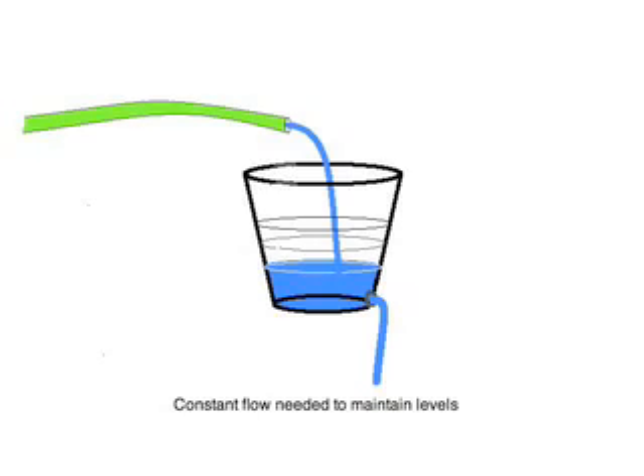With BiPAP, you don't have a closed system. You don't have an endotracheal tube and no way to keep the air from leaking out constantly. So if you tried to introduce a pre-measured volume, it would leak out too quickly. So what happens in the case of BiPAP is you have a constant flow of air that maintains a certain level. The flow will continue until it fills up to the EPAP level, and will maintain it there. When the patient starts to breathe in, the machine senses that the patient wants a breath. It increases the flow dramatically until it reaches the second level of pressure, like on this bucket. The second level would be the IPAP, and it would maintain that level for a short period of time until the flow tapers off, and the flow will crank back down to just enough to maintain the EPAP level again, all while the volume is leaking out of the system.